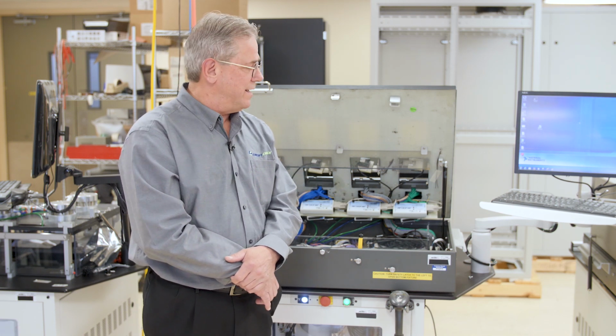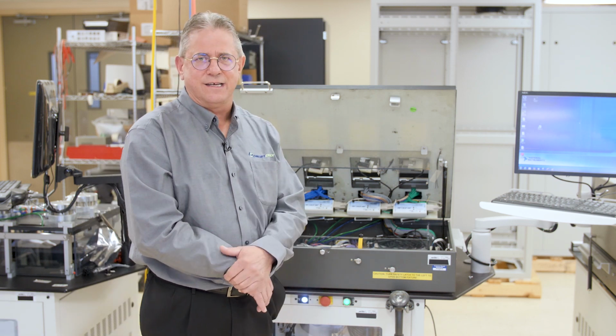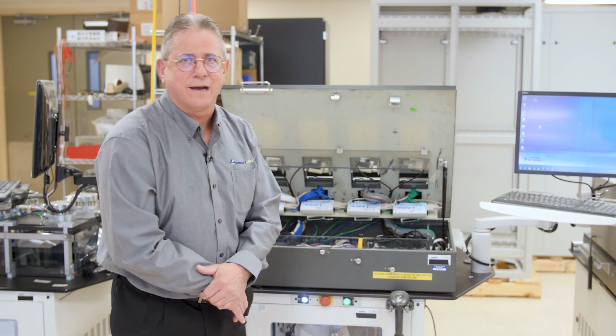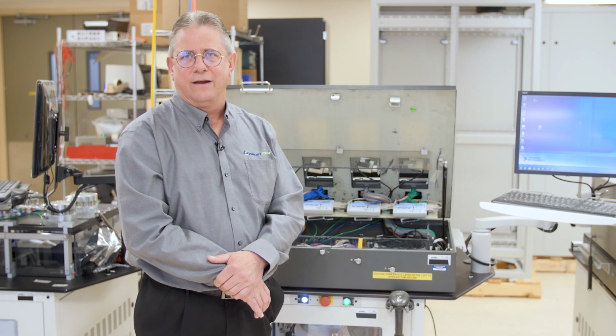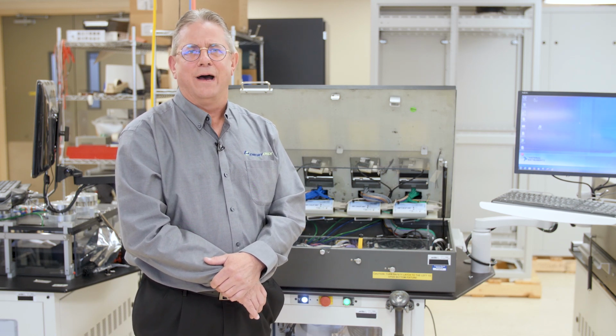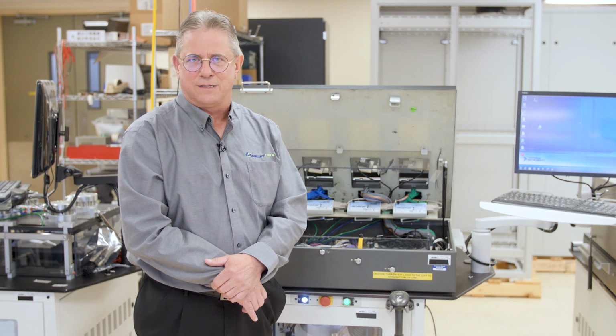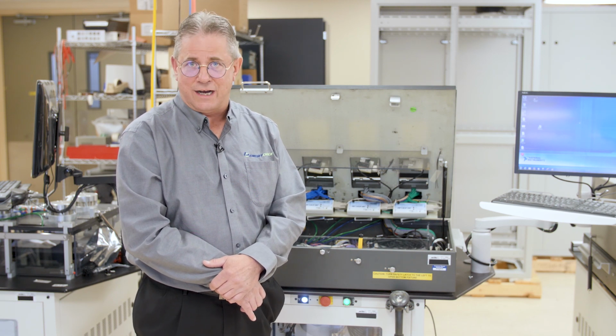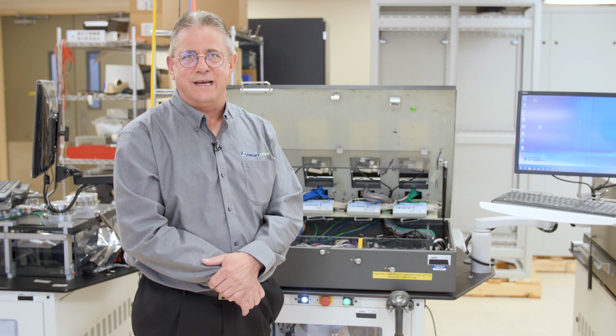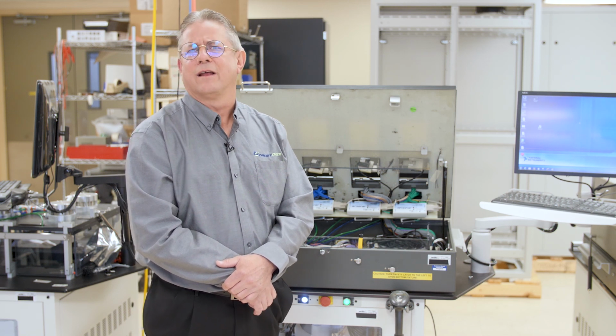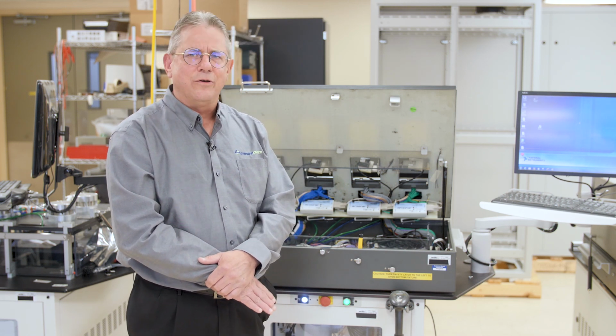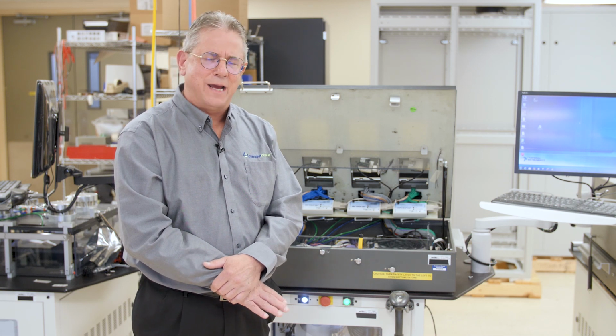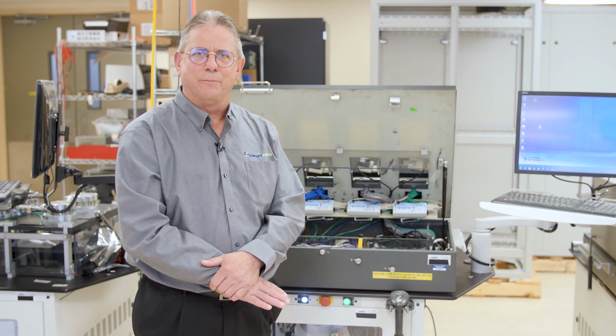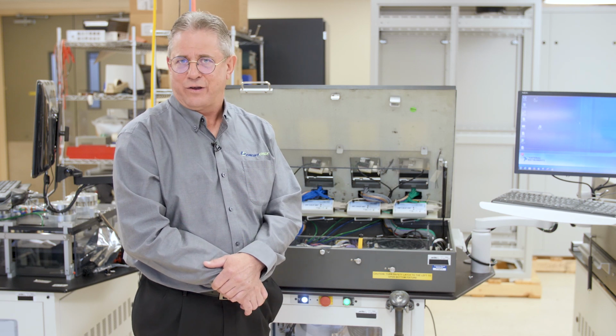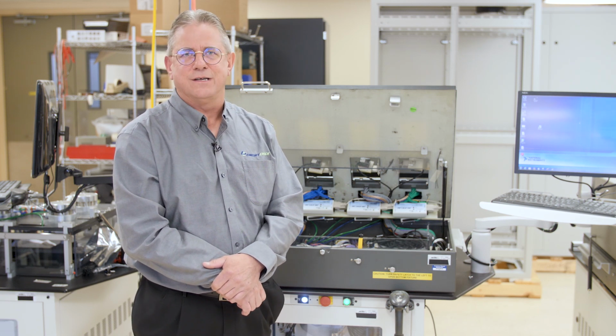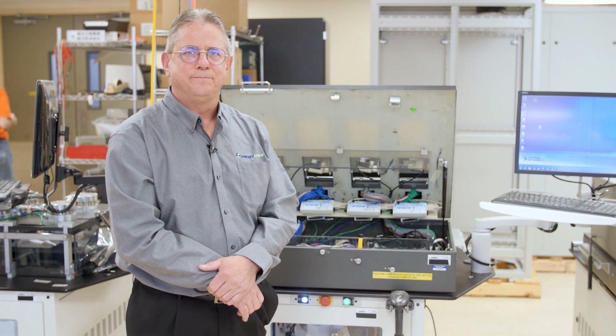The other thing to consider is the PC in the system. Whether it's embedded in the PXI chassis or a standalone PC, keep in mind that motherboards will go obsolete. We suggest using an industrial PC, and also check what the life of the motherboard is. When you come to make duplicate systems, you'll be happy you did, because you'll simply take the image off the current system, place it on the new system, and hit the ground running.